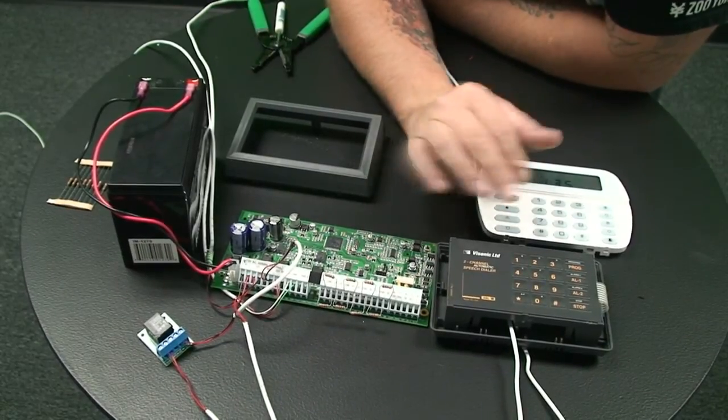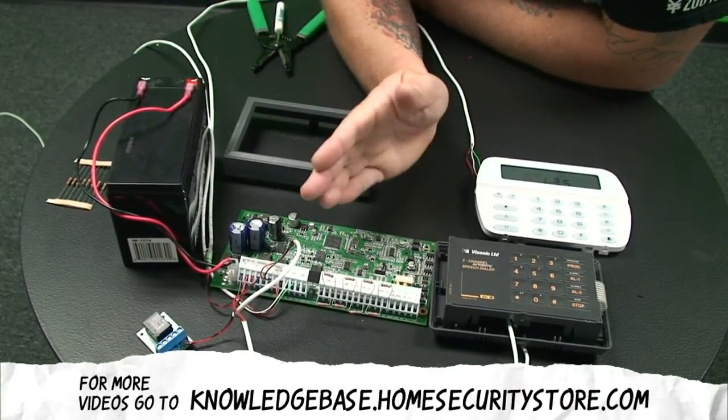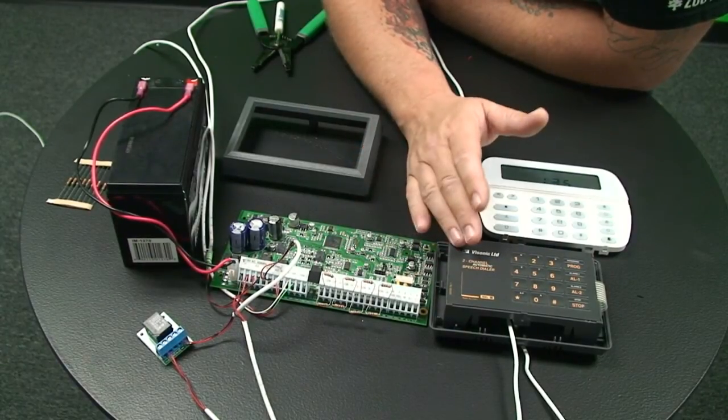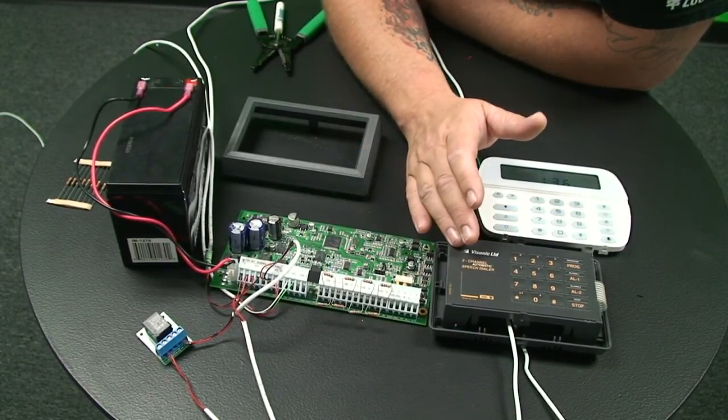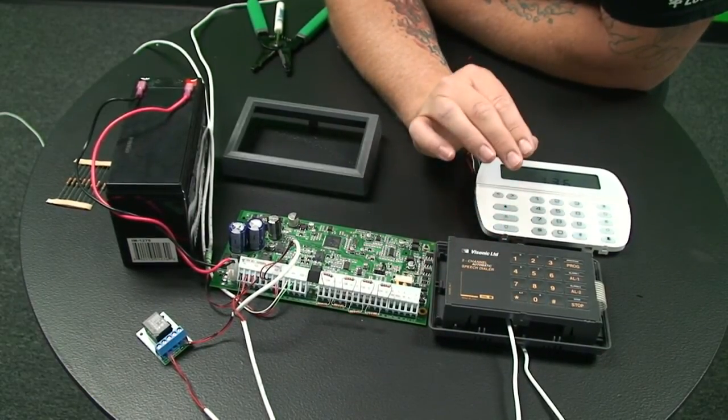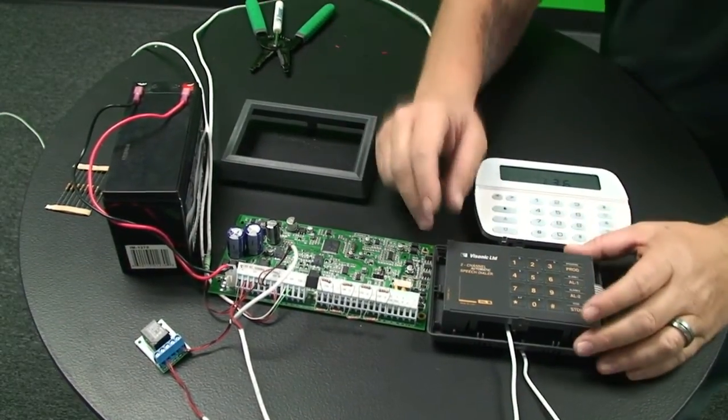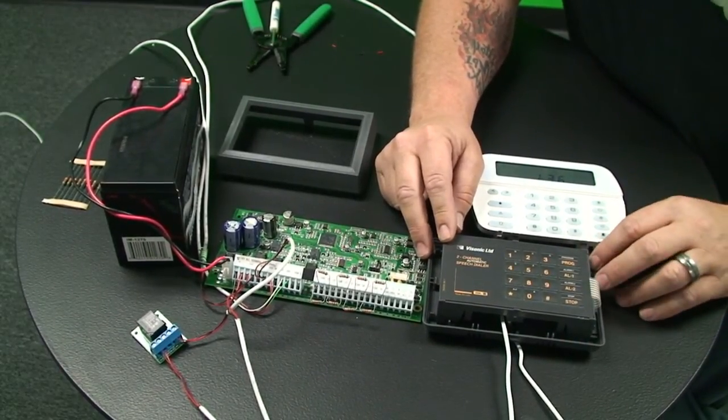And now, there's not much to program, providing that your panel's already been programmed. So the only things that we have to program is the bell circuit on the DSC panel is already ready to go. So all we have to program is the dialer telling it where we want to call. So this dialer can program with the four phone numbers. And when you're programming your phone numbers, you're going to need to make sure that they're programmed in exactly as if you were to pick up the phone and call it from your location.